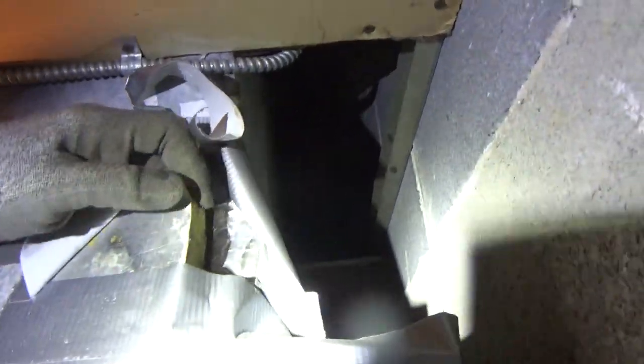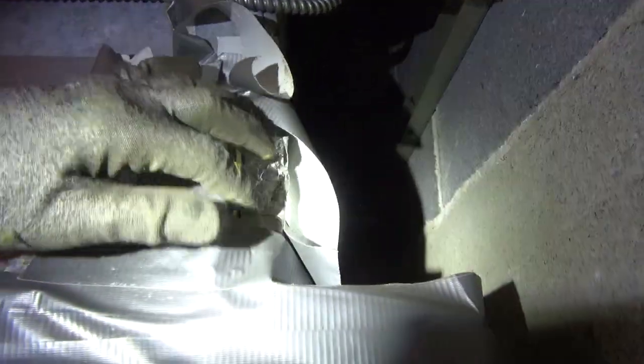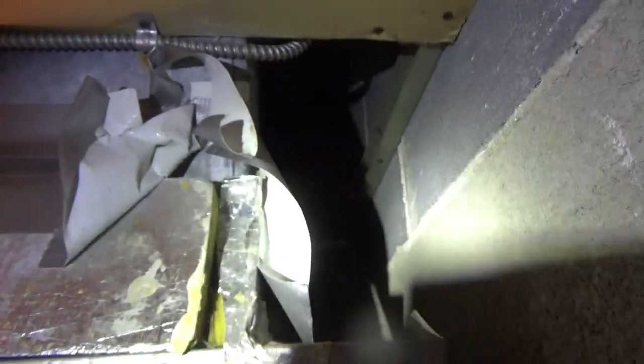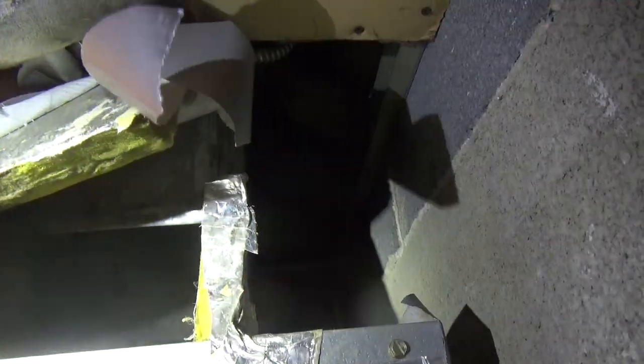So here's a problem I found. They didn't bother to mastic the supply air. So it's got major air leaks on the supply, and duct tape does not work. So if they would have used mastic up here, it would have been no problem.